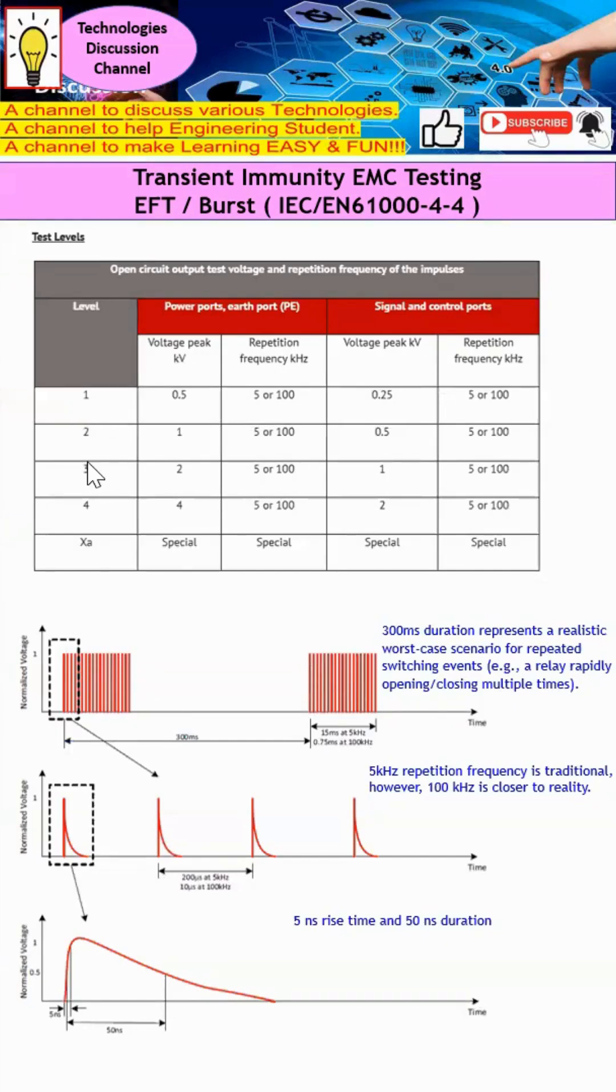Hence, we actually have these five levels of testing. You can see that one, two, three, four, and then this is under the special case. You can see that they actually have various peak voltages from 0.5 all the way to 4. The frequency to test is mainly either 5 kilohertz or 100 kilohertz. 5 kilohertz is mainly more traditional, while most of the real-time applications now actually happen at 100 kilohertz.